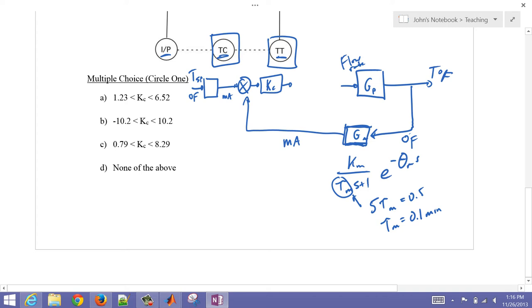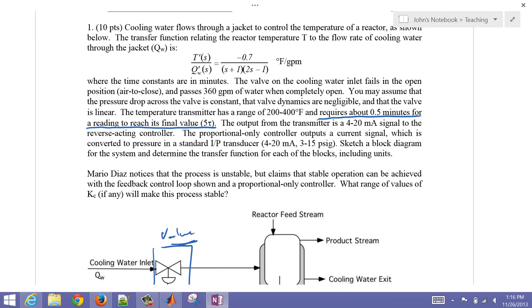Let's finish building this. What comes out of the PID controller? That's milliamps. And then you have a transfer function — you're trying to convert from milliamps to something else — to pressure. That is the KIP, the current-to-pressure conversion. And then you have a Kv for the valve. The valve on the cooling water inlet fails open, so it's air-to-close. Valve dynamics are negligible, so no dynamics in that valve.